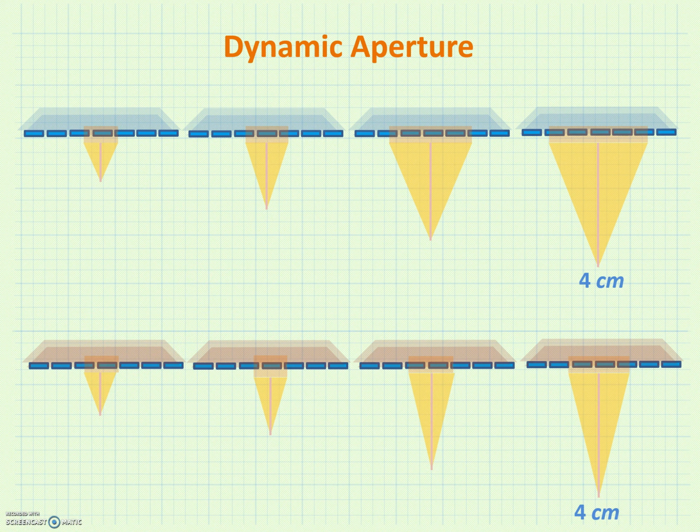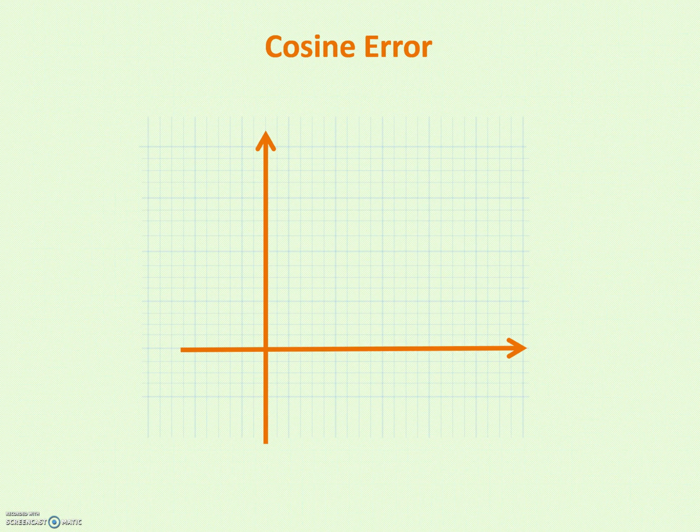And there's actually data out there for patients who are being evaluated for carotid endarterectomy. The velocity of blood moving through the carotid is used to predict the narrowing in the carotid artery, and there are patients that meet criteria for endarterectomy on one machine, and then they are evaluated by the same sonographer with a different machine, and they do not make the criteria for endarterectomy. So there can be real clinical implications for this lack of standardization in aperture width.